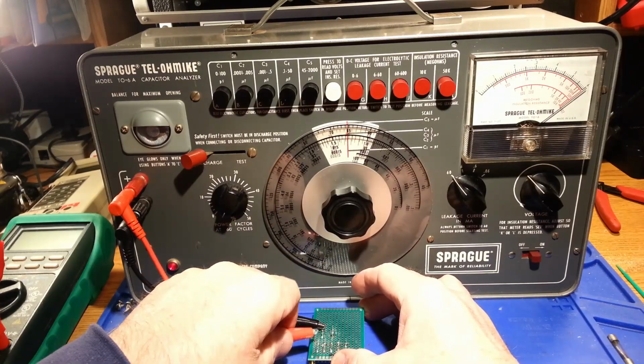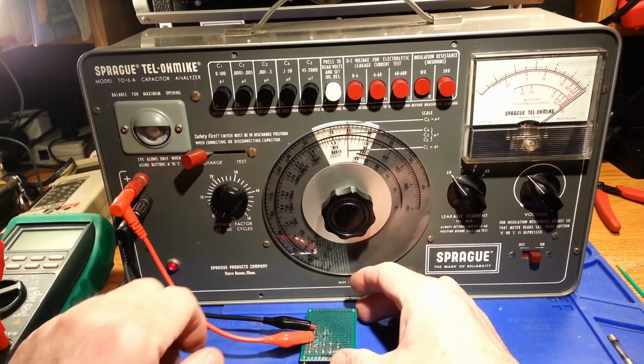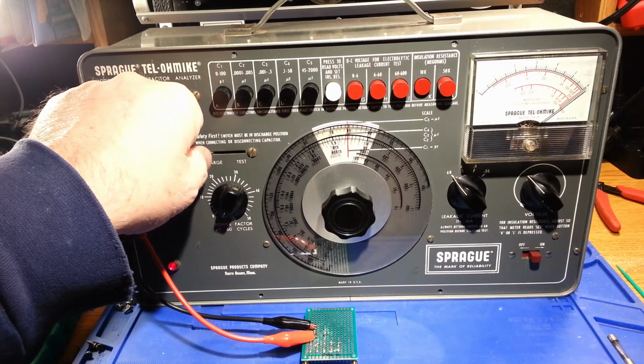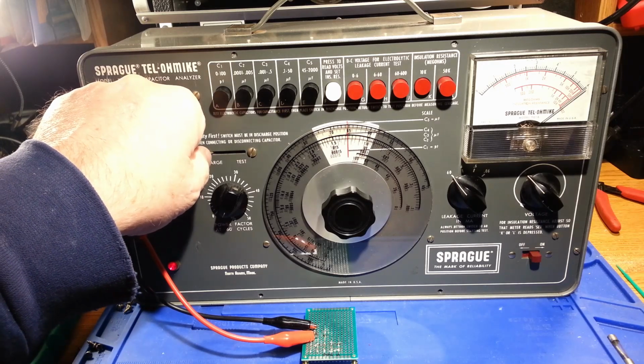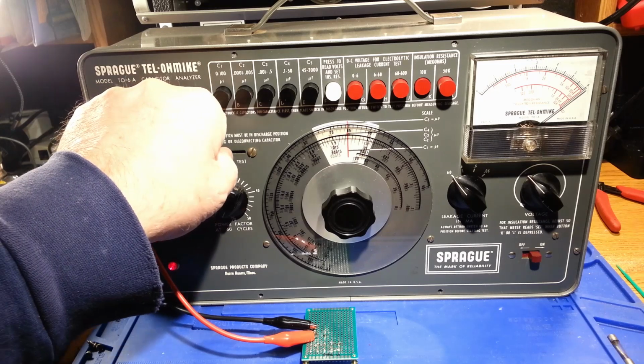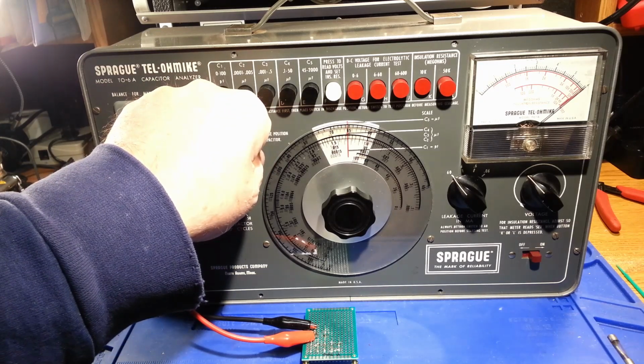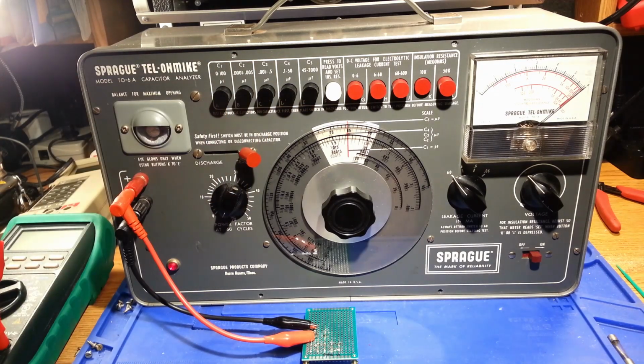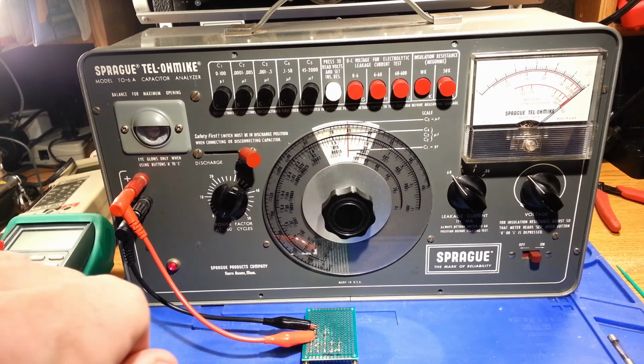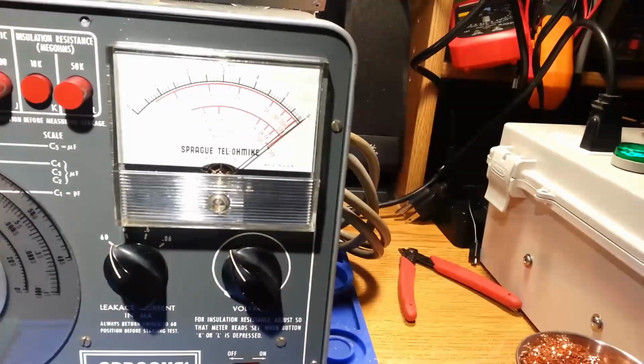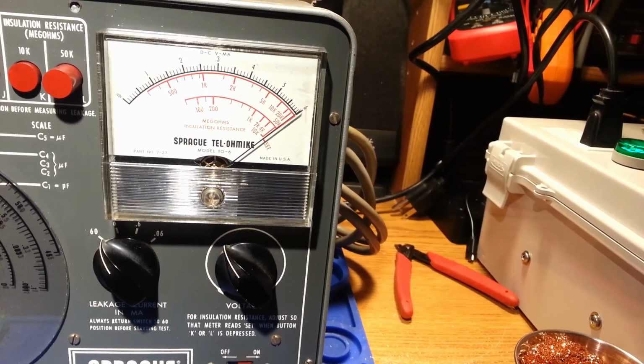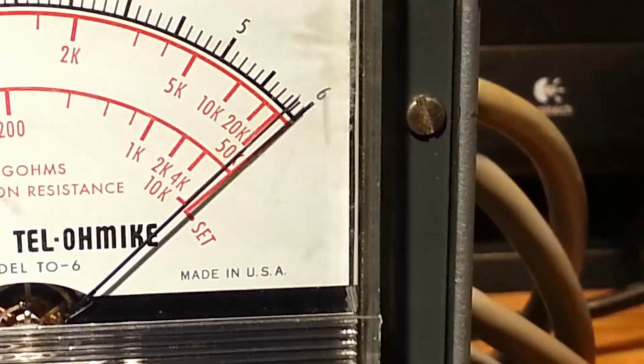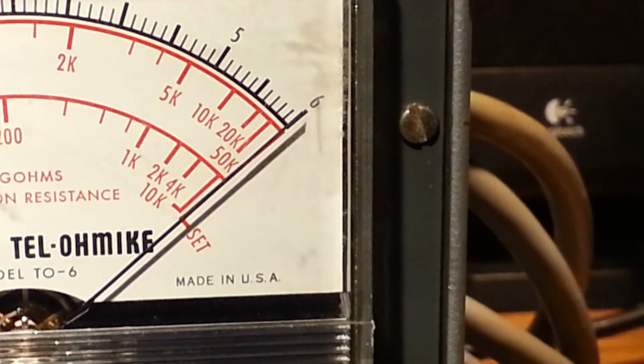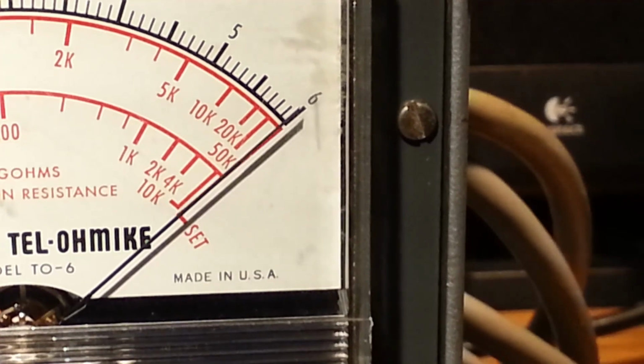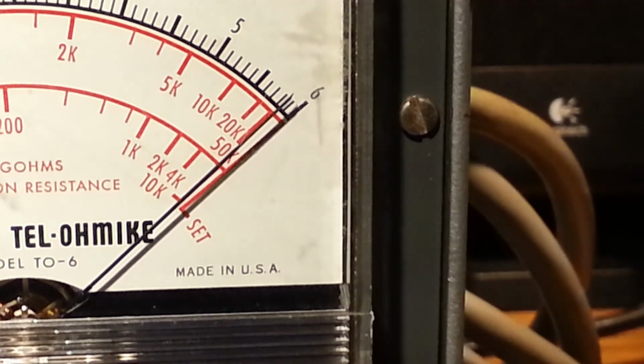One thing about this meter too is these measurements are done at a safe low voltage. This is nothing that's going to have any electric shock risk, unlike your leakage current test. So in this case, I've gone over to the test position, and my meter came down a little bit. I can go to the discharge and disconnect and reconnect. You can see that that is open circuit, and coming down, it's coming down right on the 10 kilo-megohm line.